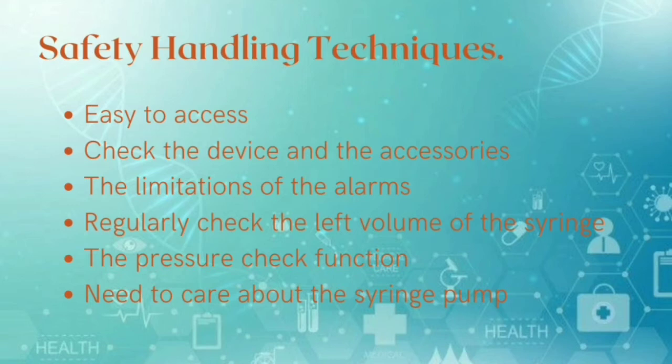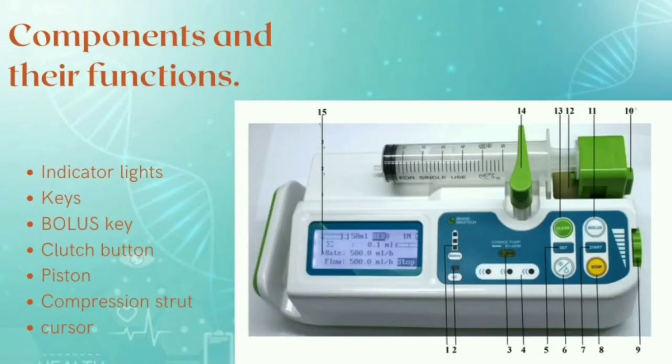The pressure check function may not work under situations like hyperbaric oxygen therapy. We need to protect the syringe pump from drop, collision or damage, and take intensive protection of blood vessels before the injection. Now let's see what are the components and their functions.